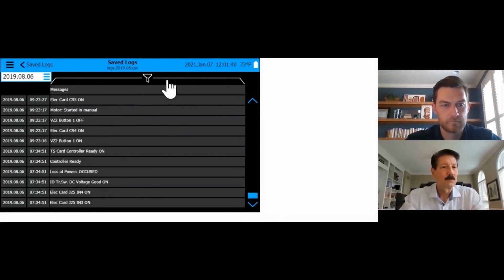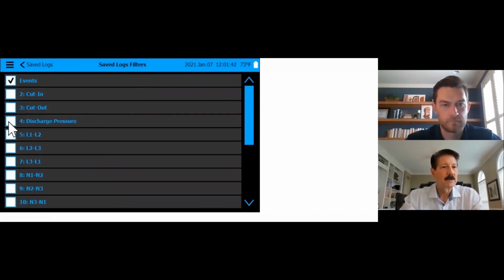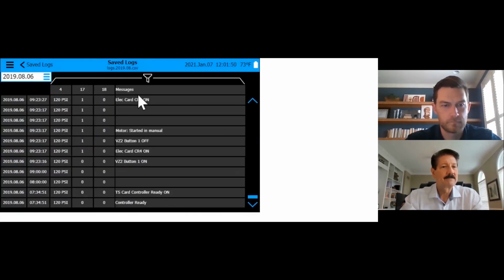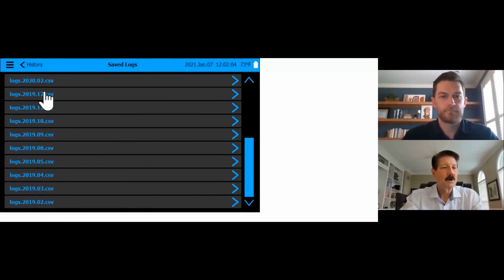If you want to get more techie, I could funnel it. I want to see discharge pressure. I want to see when the motor and the jockey ran. You see the 3 I picked. I go back and it funnels out of like 17, 18 alarms. I pick 3, and I can monitor this quite easily on the screen, and we're talking August 6th of 2019. That's what Saved Logs does for you.